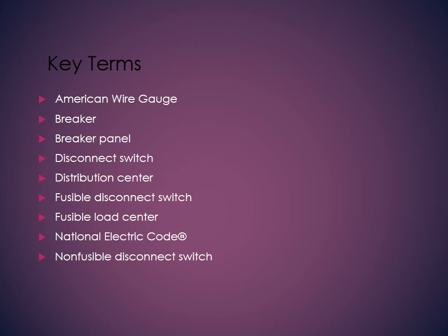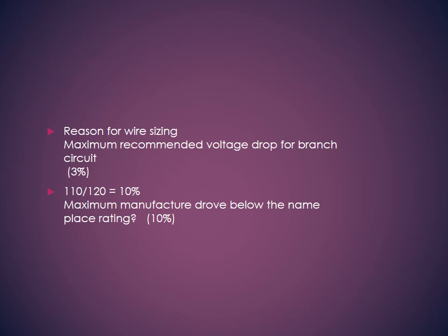National Electric Code is our guide for checking what we need to have as far as wire size and disconnect switch. So again, please remember that the maximum recommended voltage drop for a branch from the main voltage source is 3%, and when we look at the nameplate, we cannot drop more than 10%. So for any equipment, whether it be an AC, a furnace, or so on, you cannot have more drop than 10%. And if you have, for example, a very long run of wire and you drop more than 10%, you might want to increase the wire gauge. Like from 14, you might go up to 12 if you have to.